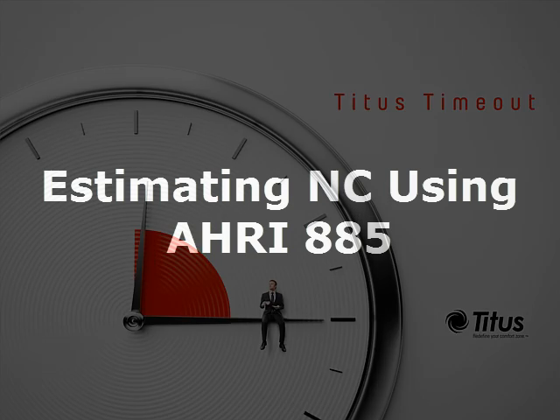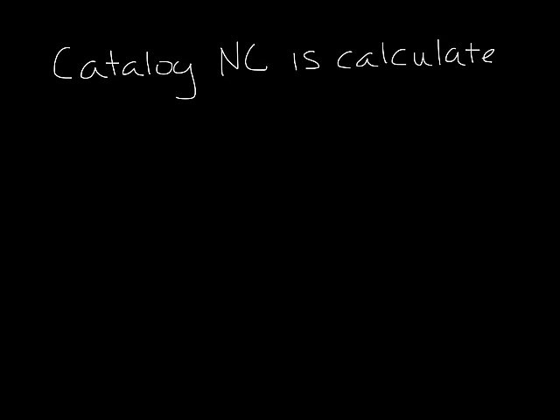I'm Jenny Abney-Civi, and today I'm going to discuss estimating NC using AHRI Standard 885. A little while ago we discussed sound power in NC, but what I didn't really get into is how NC is calculated. Catalog NC is not a measured number. It's calculated from the unit sound power using AHRI Standard 885.